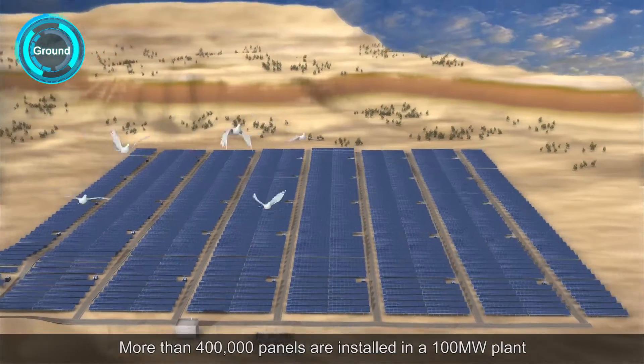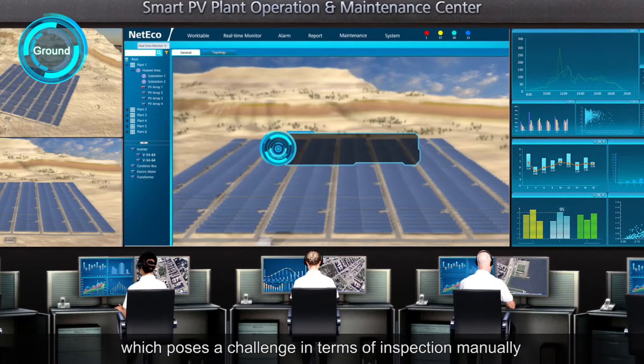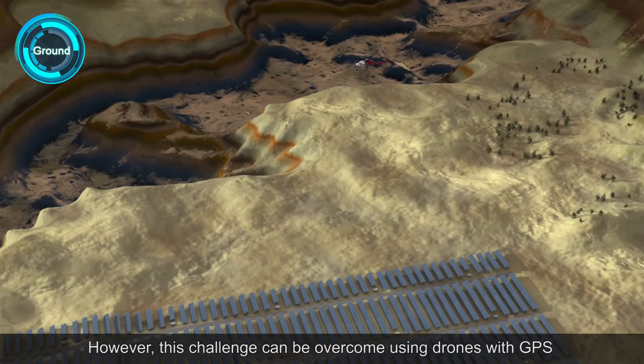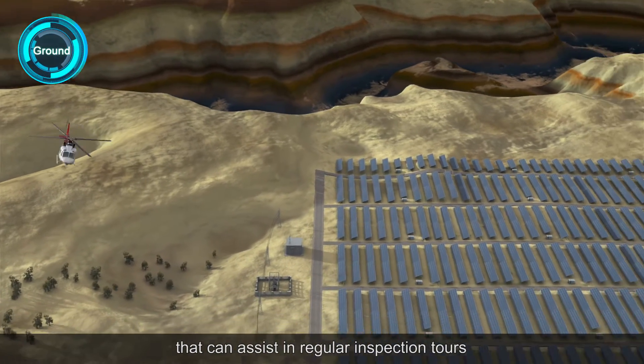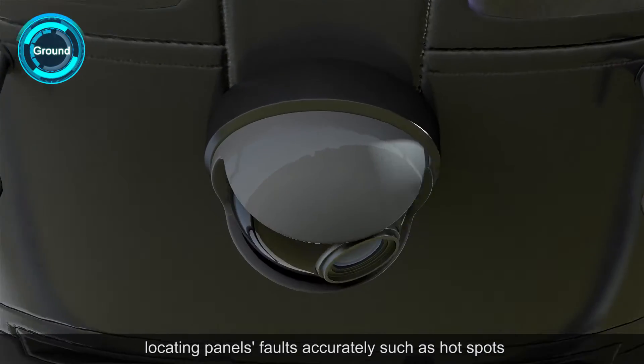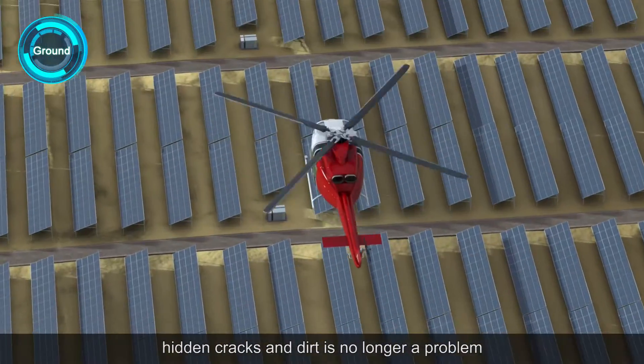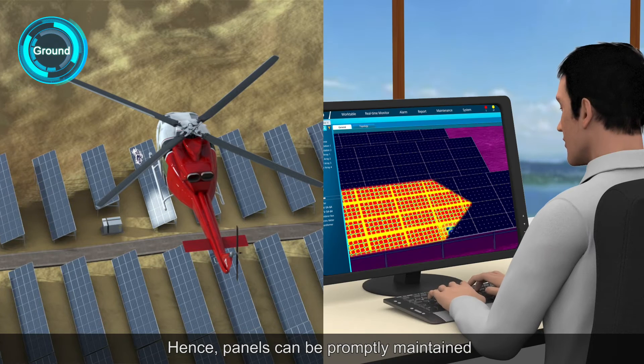More than 400,000 panels are installed in a 100MW plant, which poses a challenge in terms of inspection manually. However, this challenge can be overcome using drones with GPS that can assist in regular inspection. With IR imaging and image analysis, locating panel faults such as hotspots, hidden cracks and dirt is no longer a problem, and panels can be promptly maintained.